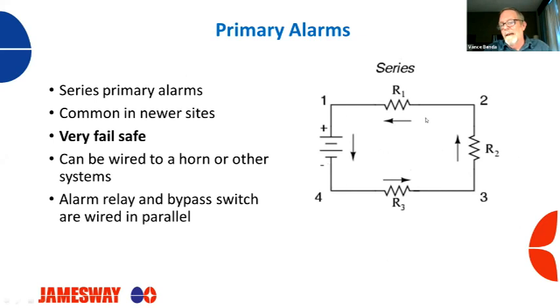So it's one path. The electricity can only flow one way it can go. And this, coupled with the fact that anytime these machines are running normally, voltage is flowing from the control box back to the control box and holding that relay open, makes this system much more fail-safe than your parallel wiring.